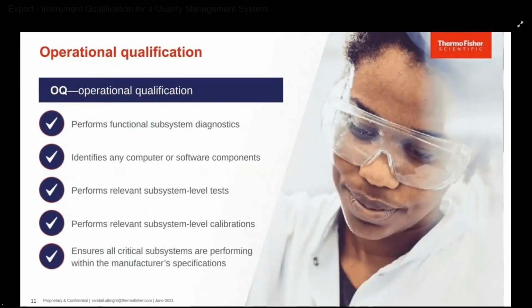Component 2 of the qualification is operational. By definition, the operational qualification will establish confidence that process equipment and ancillary systems are capable of consistently operating within the manufacturer's established limits of specification and tolerances. Additional supporting detail can be found in 820.72 inspection, measuring and test equipment, 820.80 acceptance activities, and subpart N 820.200 servicing. Thermo Fisher Scientific breaks down the operational section into effective subsystems of our instrument and equipment. Some examples of subsystem testing are the internal self-test diagnostics, thermal testing, lamp or laser alignments, and optical calibrations.